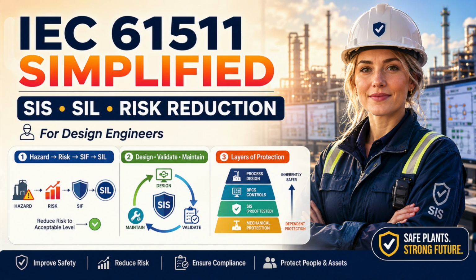And when you review your next safety instrumented function, do not begin by asking what SIL it carries. Begin by asking what hazard it must stop, and whether the complete system can still keep that promise when the plant is under its worst credible conditions.